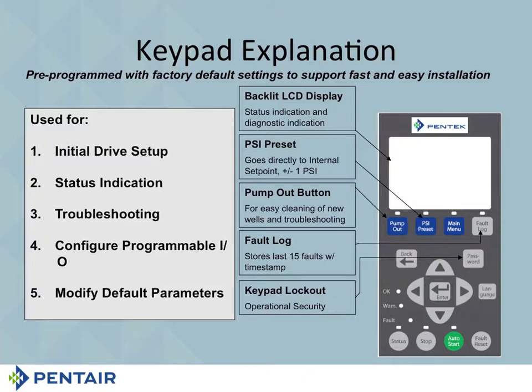We do have LED status indicator lights, all right? Now, they have nothing to do with faults, except that the red one's going to come on when you have a fault. When there's a warning, the yellow one will come on, and if everything's running just fine, you've got power to the drive, the green one will be on that says okay. That's the only time you're going to see those LED lights, and you don't have to count them for fault information and like that, because we're just going to tell you right on the screen what's going on.